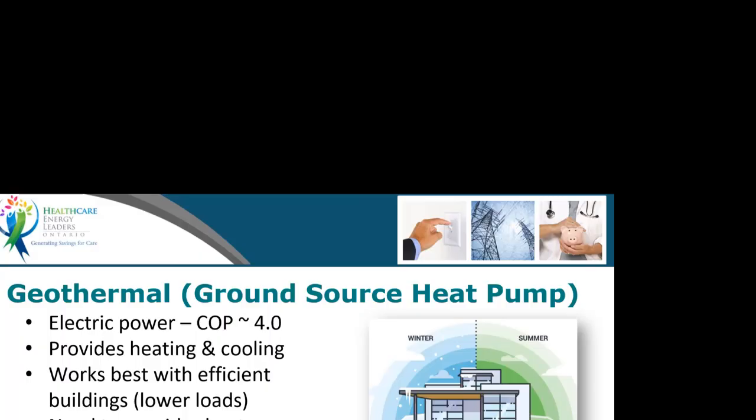But I was looking at Electrical or Mechanical Business News a little while ago, and this is the Quebec City Hospital, and they were talking about the engineering of the geothermal system. And basically what they said here was a lot of engineering was put into maximizing heat recovery before we sized the geothermal system, said the engineer. It's much cheaper to recover internal heat versus digging around in the ground to reach the heat in the soil. So we took as much advantage as possible of existing energy in the building.